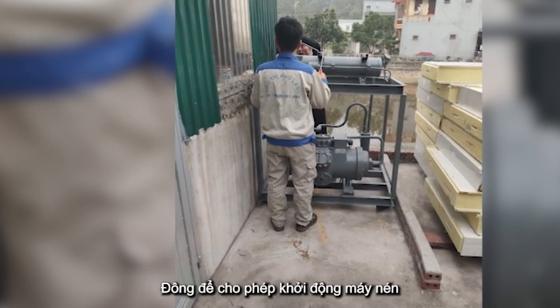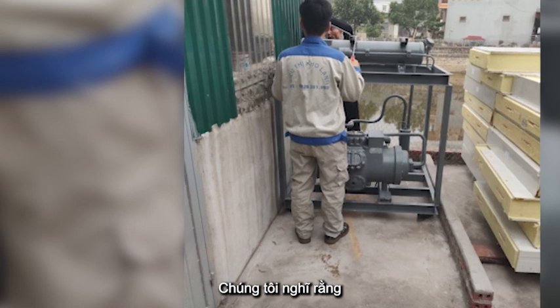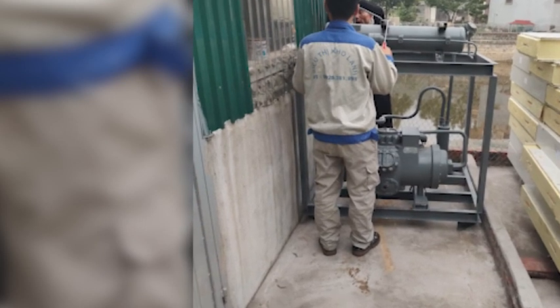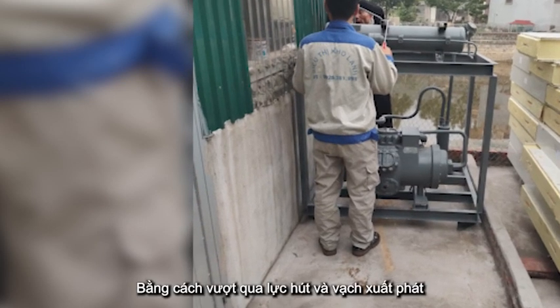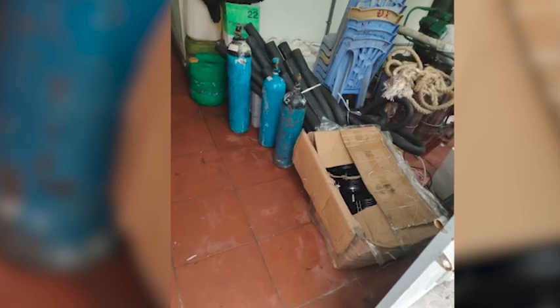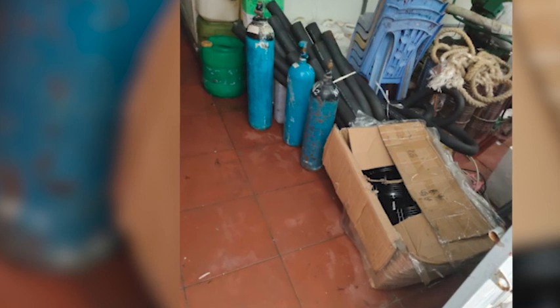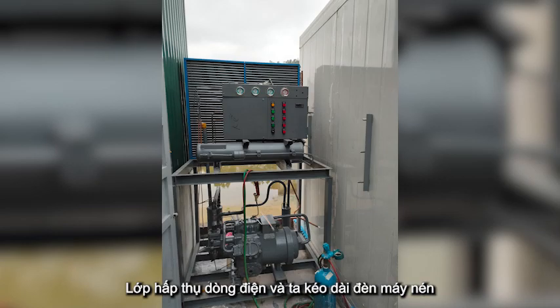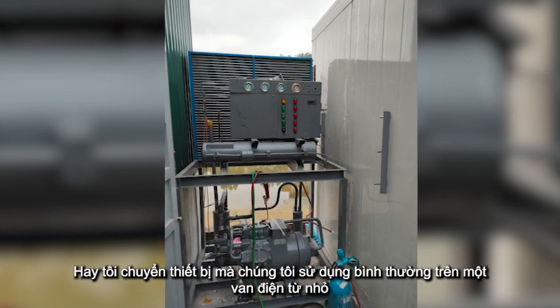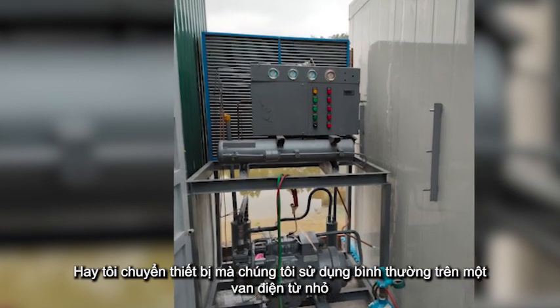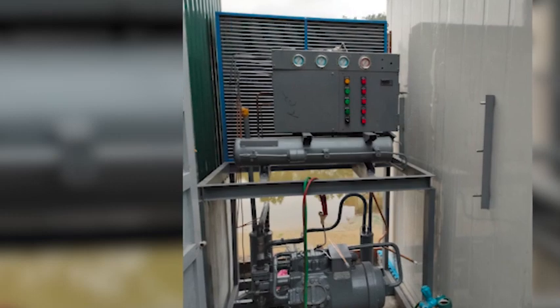The goal is to allow the compressor to start without charge, bypassing suction and discharge line for some seconds at the beginning. This way we get less absorbed current and we lengthen the life of the compressor. For the bypass device we use normally a small solenoid valve.